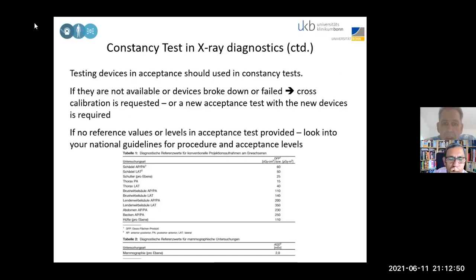But you will figure out that maybe your department has no standard patients. So what will happen if you don't have standard patients? Then you will exceed those reference levels. And in Germany, we then have to note down why we exceeded those reference levels. This could be overweight or an intensive second image or whatever. There are several reasons why this could happen. But you have to be sure that you know what reference level you are testing against. So that is your upper threshold, I would say.